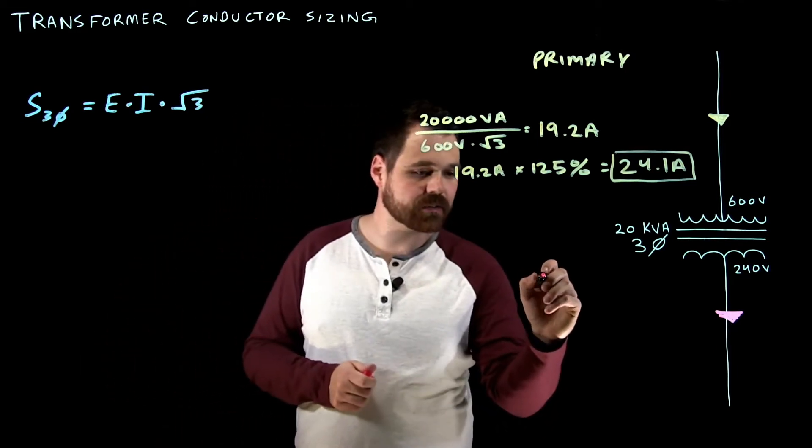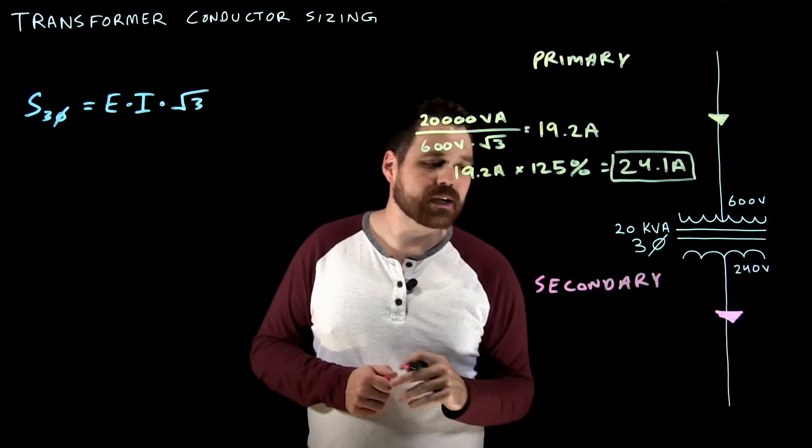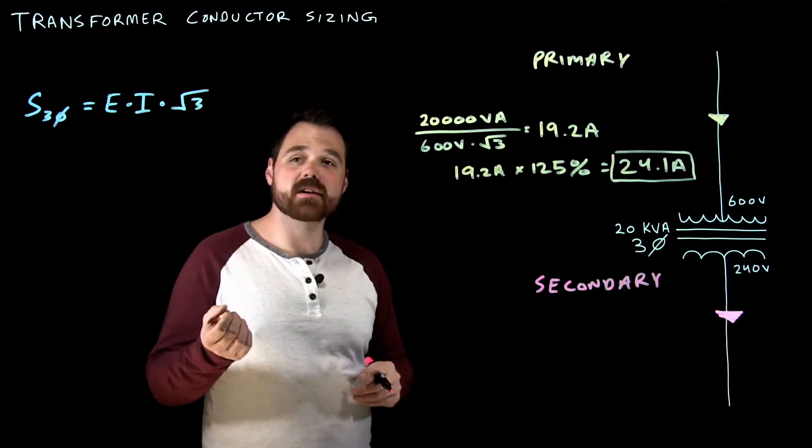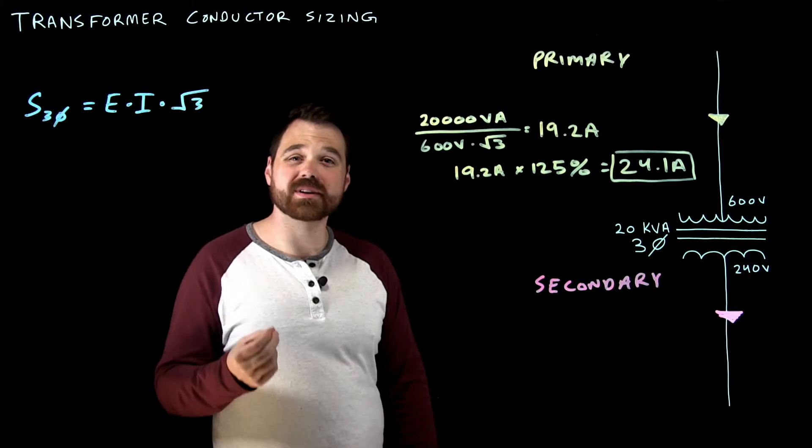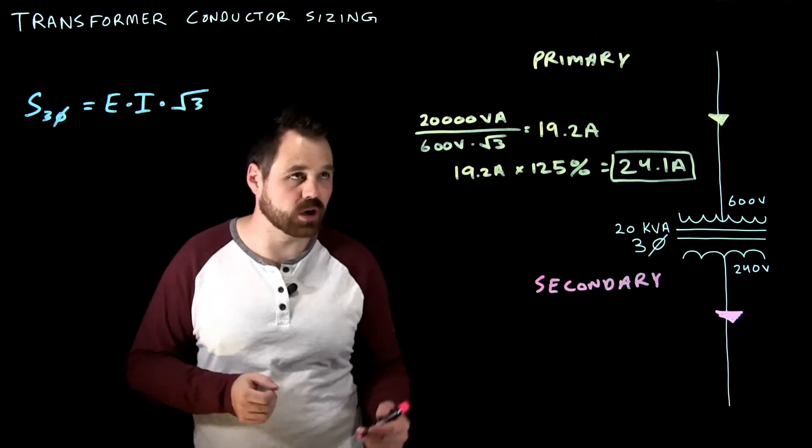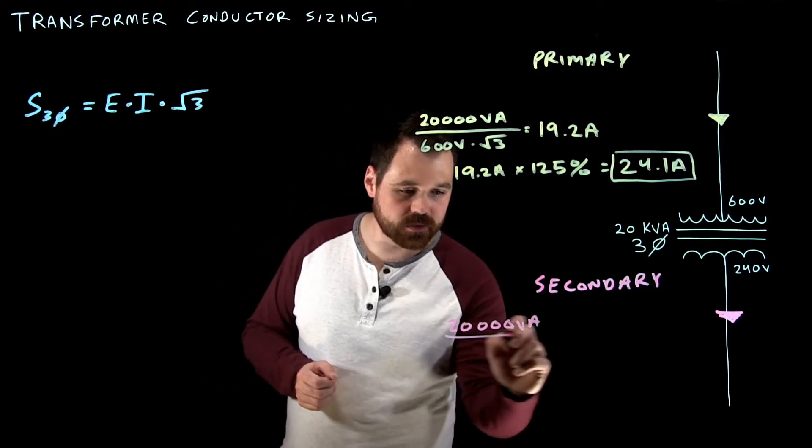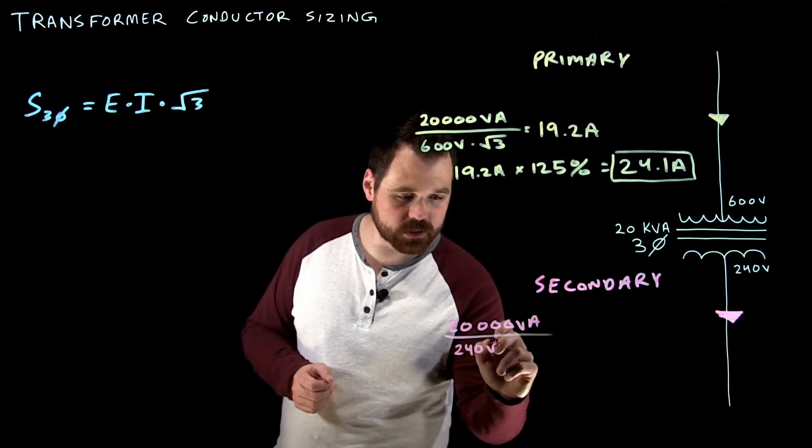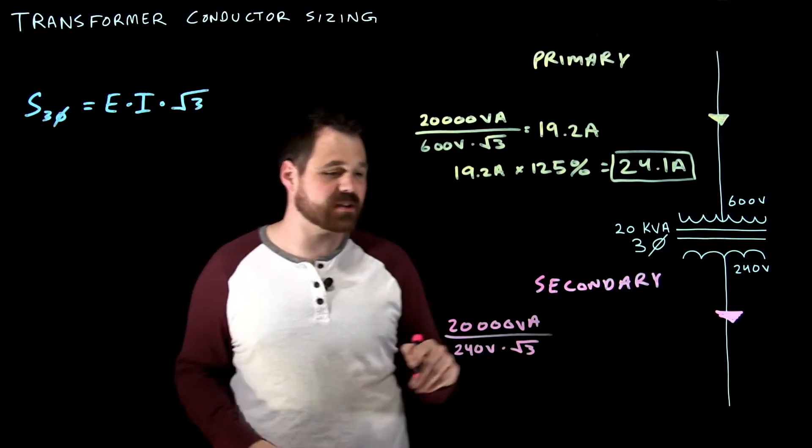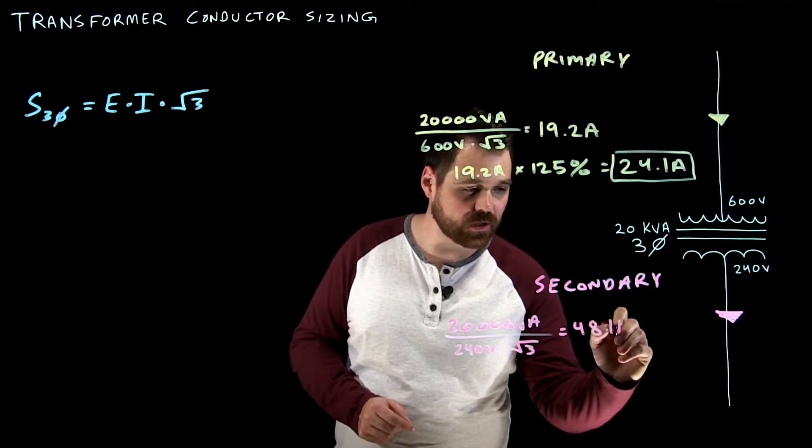That brings us down to the secondary. Now the secondary is actually the exact same process. So it tells us that the secondary conductors need to be rated for 125% the rated secondary current of the transformer. So do the exact same process 20,000 VA divided by 240 volts. Again, we don't want to forget that root three because we are talking about a balanced three phase system here.